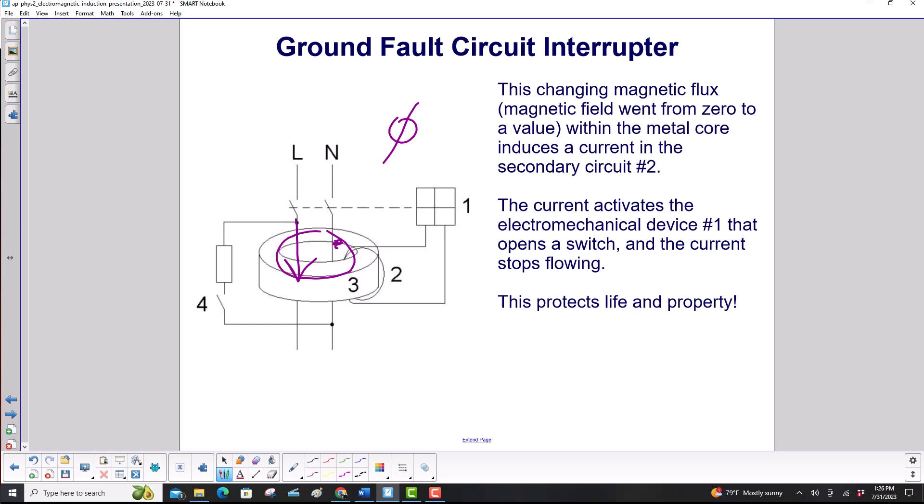A changing magnetic flux within the metal core induces a current in our secondary circuit here. The current activates the electromechanical device that opens the switch, and the current stops flowing. And all of this business is incorporated into that little GFCI outlet. So it's canceling the circuit right at the source of where your plug is. This protects life and property.